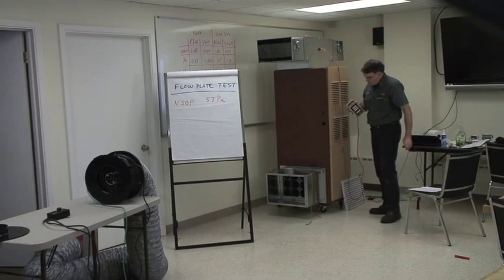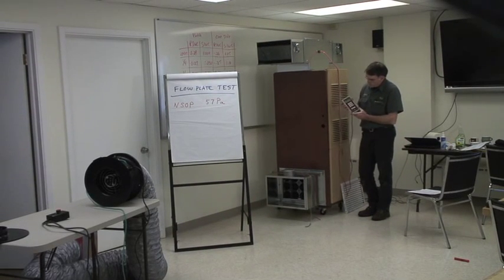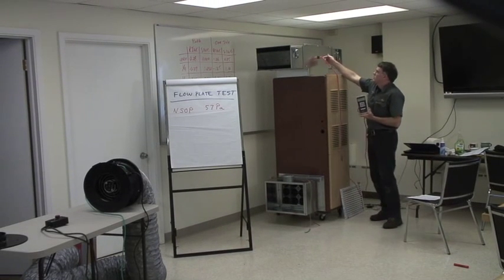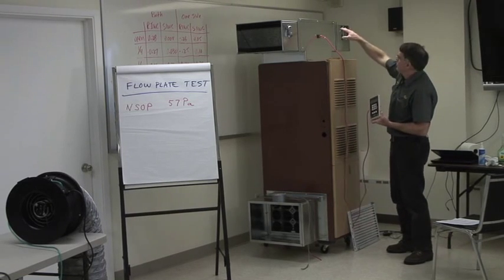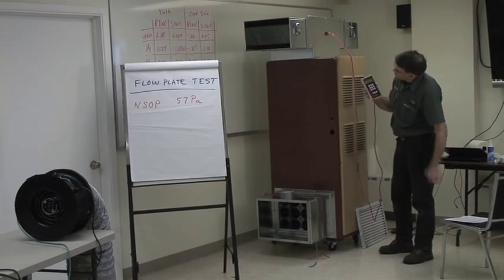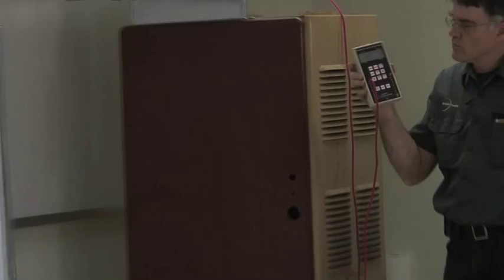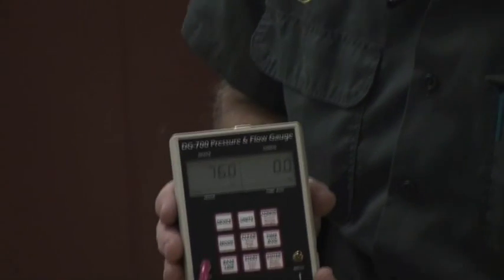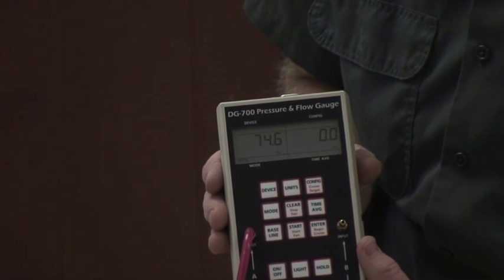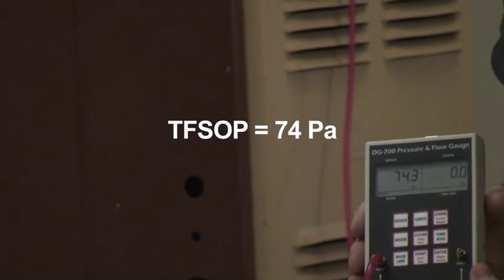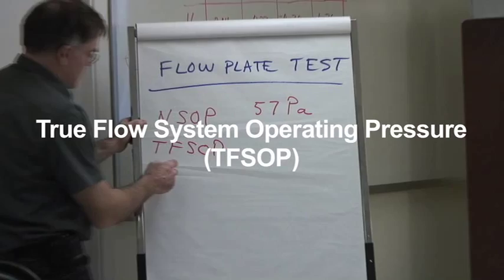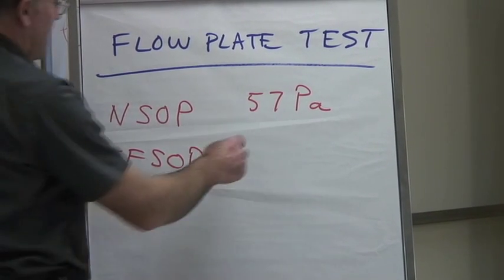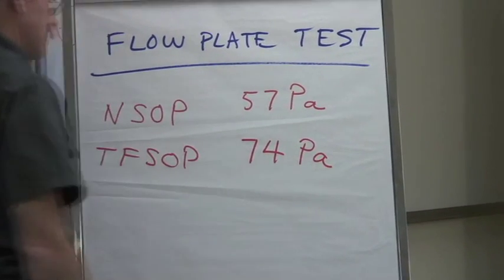Now before I connect up to the plate, I'm going to re-measure my supply static pressure. I didn't have to do anything other than replace the filter with the plate. Didn't have to move this, it has a magnet to keep it on. All I do is look back at the number on the gauge. In this case, it's around 74 or 75 Pascals, moving around a little bit. I'll just choose 74. The abbreviation we use for this is TFSOP for True Flow System Operating Pressure, 74 Pascals.